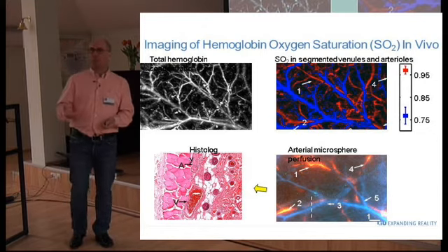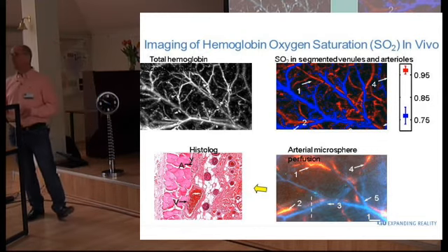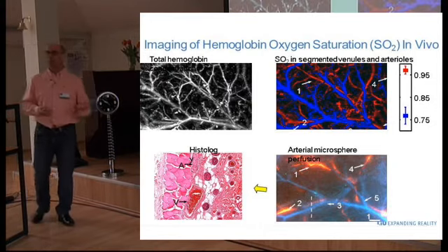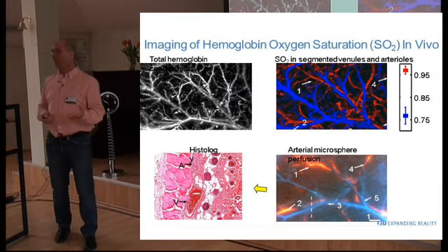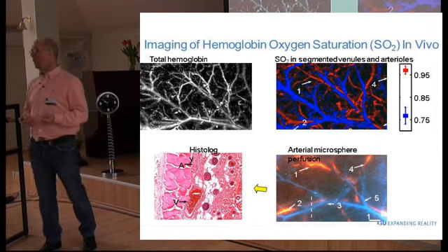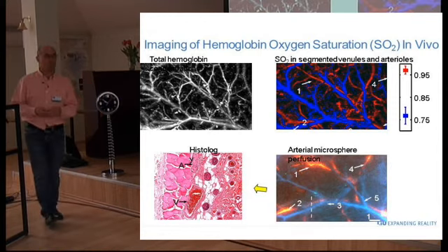That means that you can also reach higher depth, up to 5 to 6, perhaps 7 centimeters into the tissue, compared to OCT, which gives you about 0.5 millimeter or 1 millimeter. So there is a vast difference in what we will see.